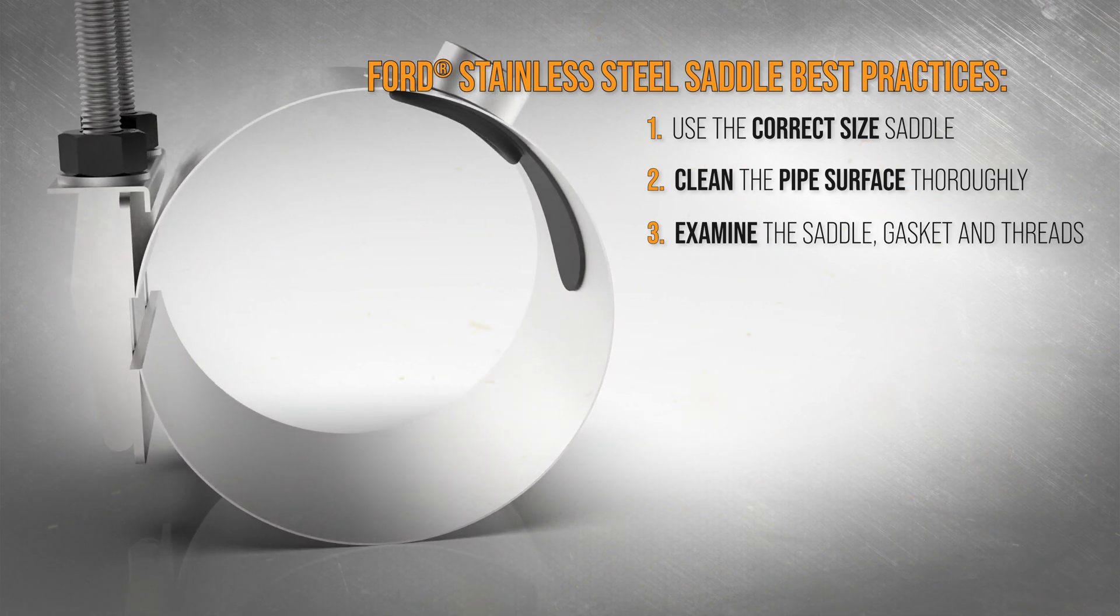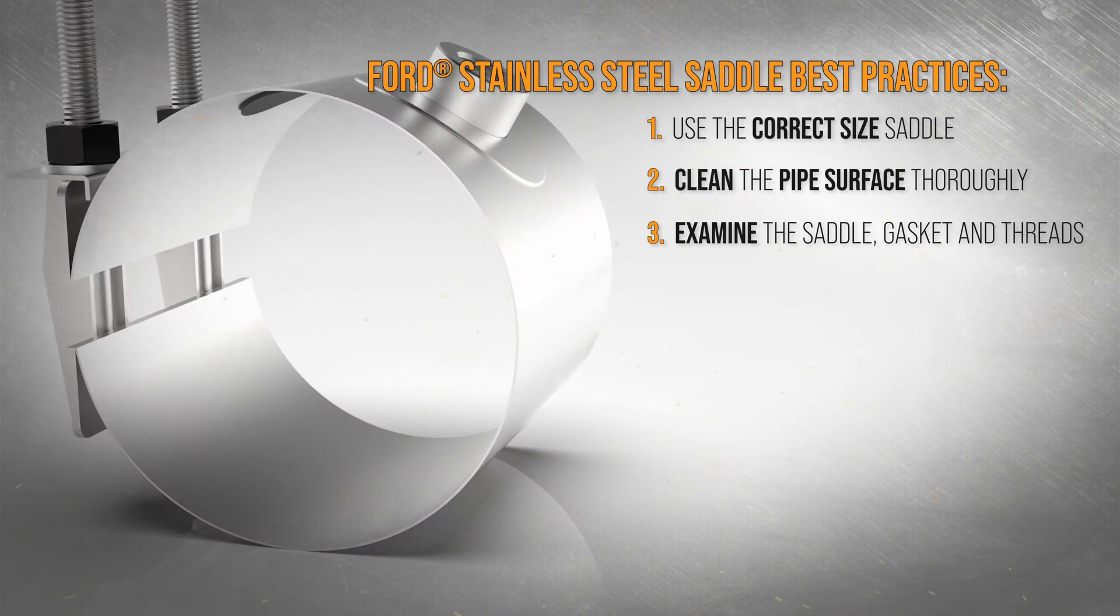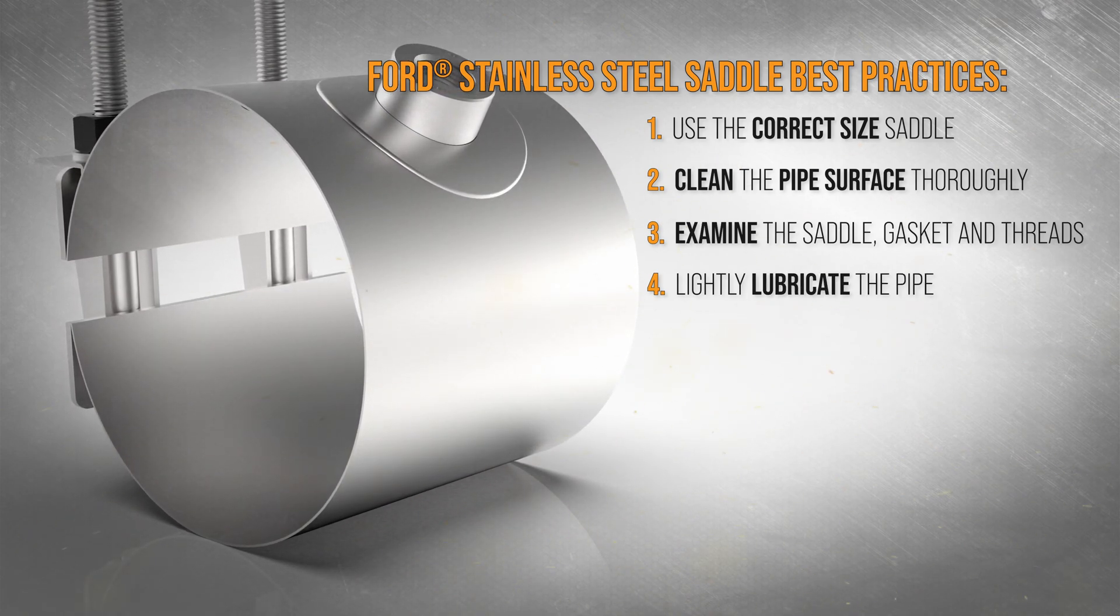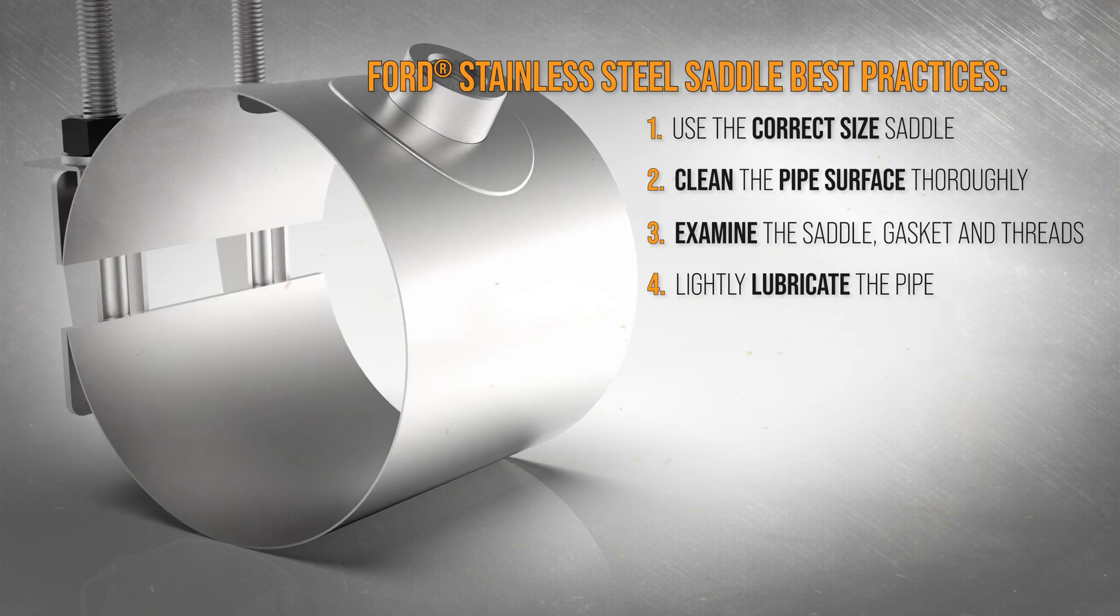Examine the saddle gasket sealing surface and the clamping stud threads for debris or damage. Lightly lubricate the pipe under and beyond the gasket contact area with a thin coating of pipe joint lubricant.